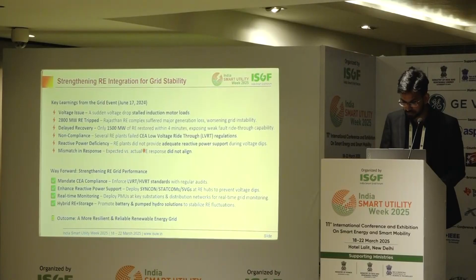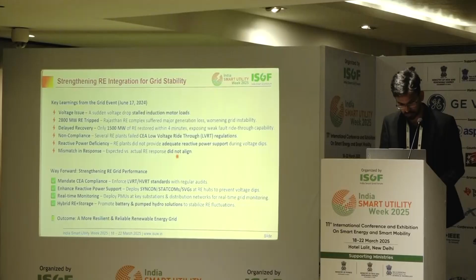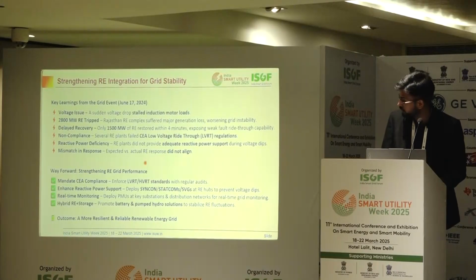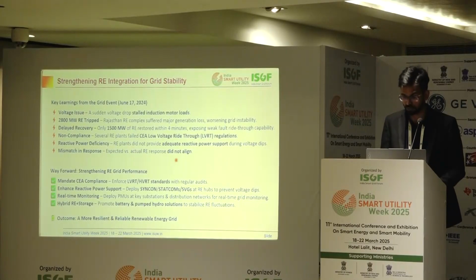Also, there was reactive power deficiency. The stalling of motors started absorbing reactive power, but due to reactive power deficiency at load centers, voltage decreased further and reached 0.74 per unit. Also, in the model validation, we saw the expected and actual RE response were not aligned with each other.